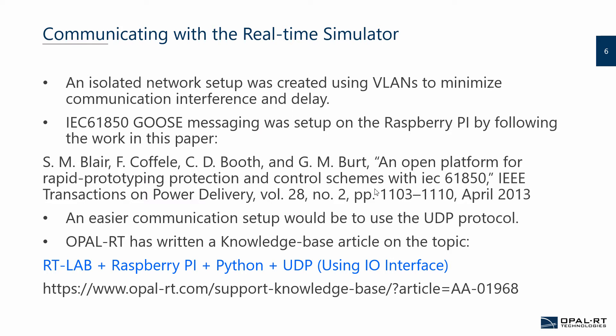The microgrid communications were done over Ethernet, where an isolated network setup was created using VLANs to minimize the communication interference and delay. This replicates a real power system network in a better way, as power system communications are normally isolated. The IEC61850 GOOSE was set up on the Raspberry Pi with the help of the paper listed here, an open platform for rapid prototyping protection control schemes. However, it's worth mentioning that an easier and more straightforward communication setup between the Pis and the simulator would be to use the UDP protocol. Opal RT, in fact, has written a knowledge-base article on the topic, which you can find if you search for any of the following keywords: RTLAB, Raspberry Pi, Python, and so forth.